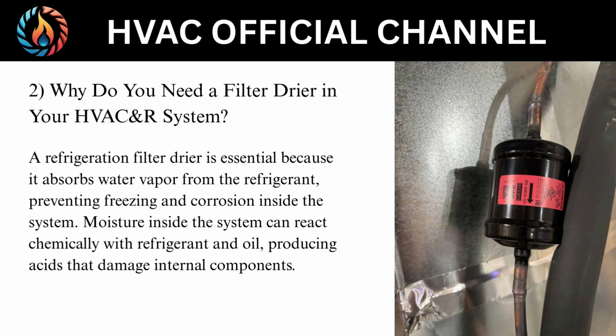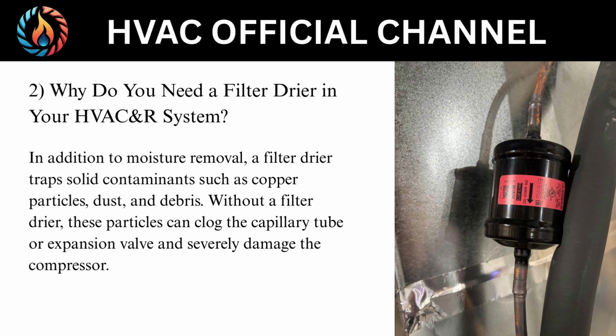2. Why do you need a filter dryer in your HVAC&R system? A refrigeration filter dryer is essential because it absorbs water vapor from the refrigerant, preventing freezing and corrosion inside the system. Moisture inside the system can react chemically with refrigerant and oil, producing acids that damage internal components. In addition to moisture removal, a filter dryer traps solid contaminants such as copper particles, dust, and debris. Without a filter dryer, these particles can clog the capillary tube or expansion valve and severely damage the compressor.